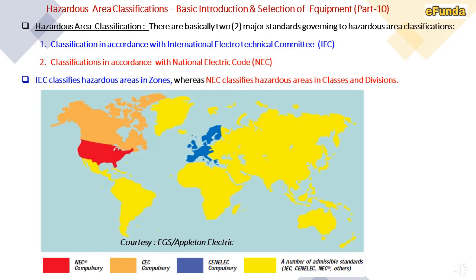There are basically two major standards governing hazardous area classification. One is classification in accordance with the International Electrotechnical Committee, that is IEC; and classification in accordance with the National Electric Code, that is NEC. IEC classifies hazardous areas in zones, whereas NEC classifies hazardous areas in classes and divisions. One can see in the picture where applicable standards are used — NEC shown in red, with other colors indicating respective zones.